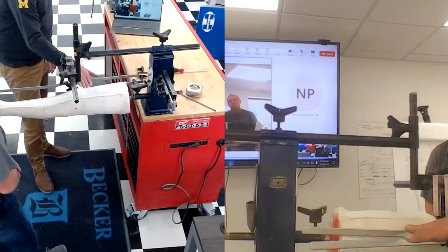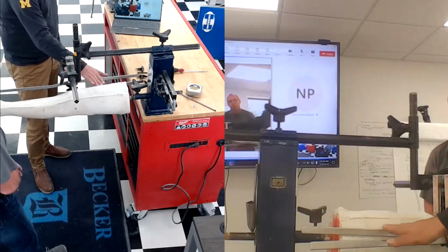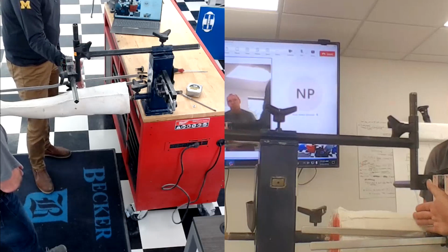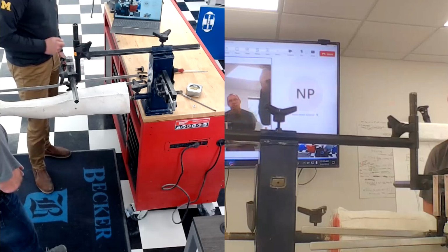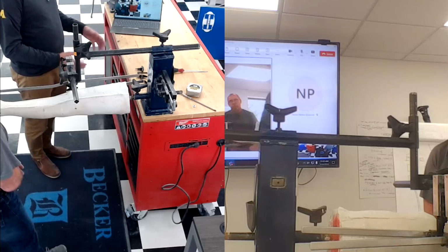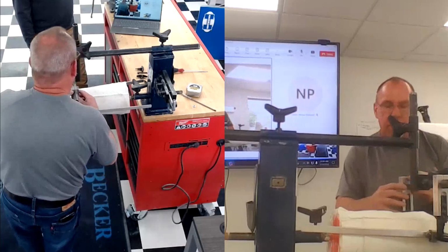flexion extension, that's what aligns that for you, by bringing the alignment tool from the one side onto the other side, putting a square across, or, we use our eyes for the most part across that joint casting, but you can be a little more objective by putting a level or a square across there too, and that helps you make sure you've got good parallel alignment. So that's especially important in the case where you don't have that alignment rod to ensure the connection between the two sides.